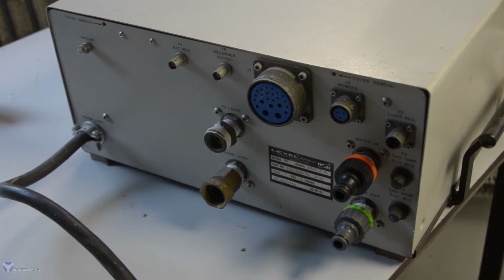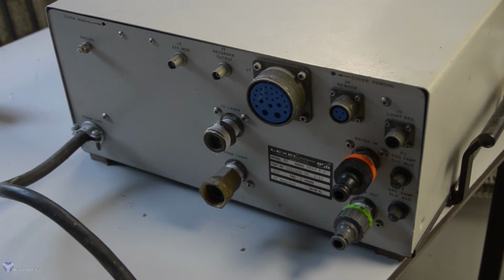This is the back of the power supply, which you see a lot of connections. The big one is for the laser head. That of course carries the power to the laser tube, the cathode, and stuff like interlocks, emission indicators. And of course there are water cooling connections, and the power supply itself is also water cooled. It also generates quite a lot of heat, and it has to be carried away. And you also see the connections of the water cooling that run to the head.